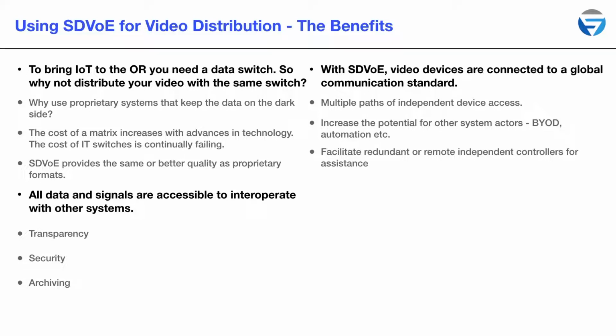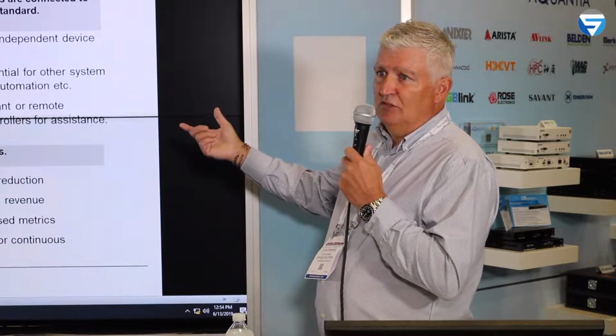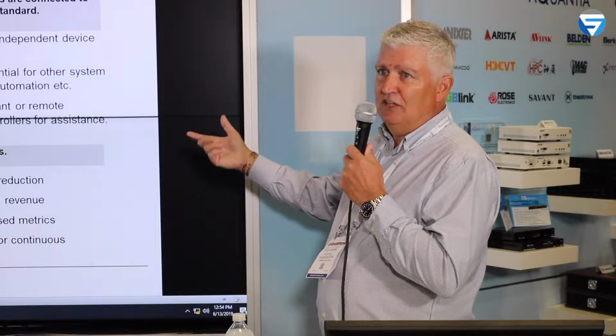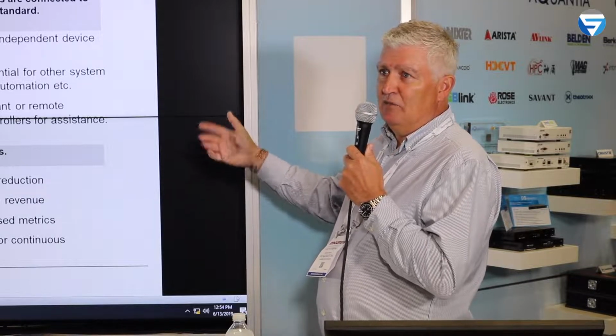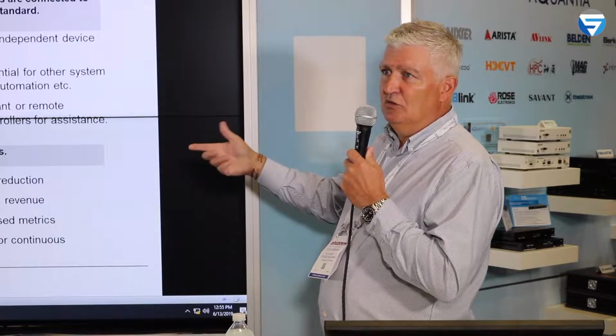So the only device that a medical physics guy has in his office is a device connected to the hospital network. So only by using the hospital network can he go to the OR without physically going there. He can log in over the IP into the controller, fix the problem. To run a redundant system is a $100 Raspberry Pi. You can actually have an emergency system backing up the main controller with a simple GUI to do the switching for you for emergencies. It costs you $50 or $100 for a Raspberry Pi.